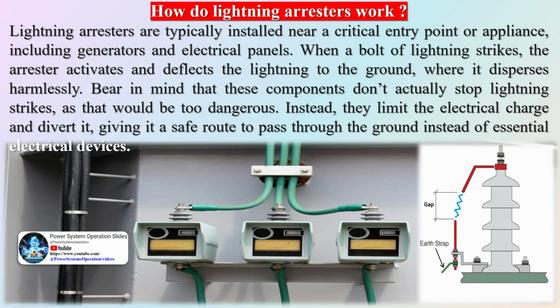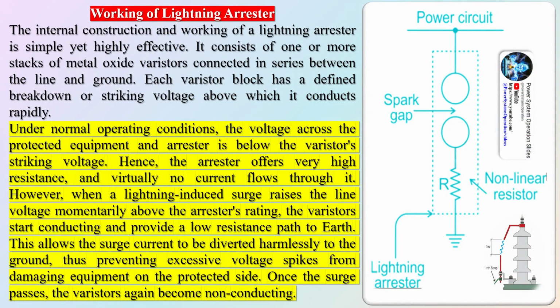Lightning arresters are typically installed near a critical entry point or appliance, including generators and electrical panels. When a bolt of lightning strikes, the arrestor activates and deflects the lightning to the ground, where it disperses harmlessly. Bear in mind that these components don't actually stop lightning strikes, as that would be too dangerous. Instead, they limit the electrical charge and divert it, giving it a safe route to pass through the ground instead of essential electrical devices. Working of lightning arrestor.